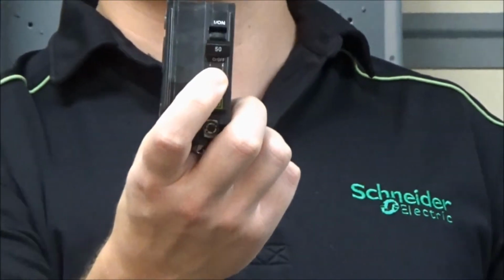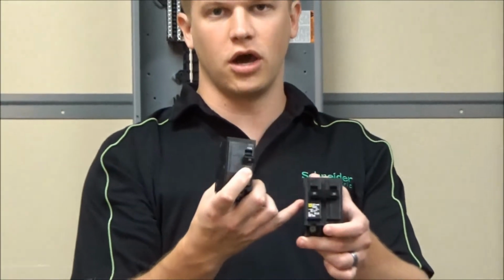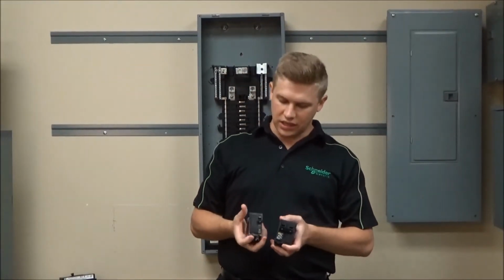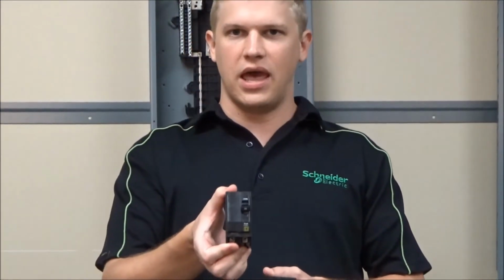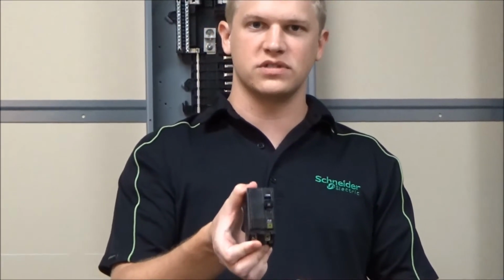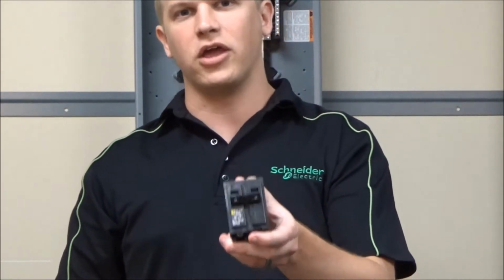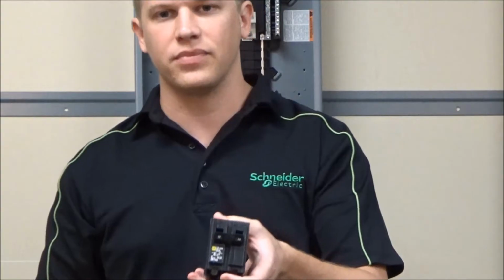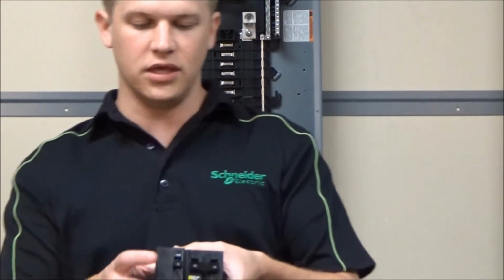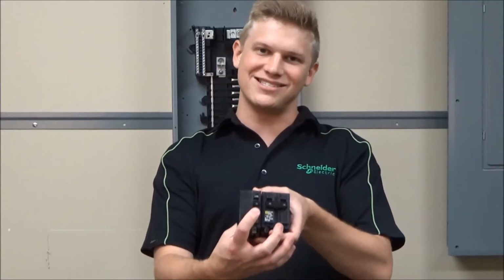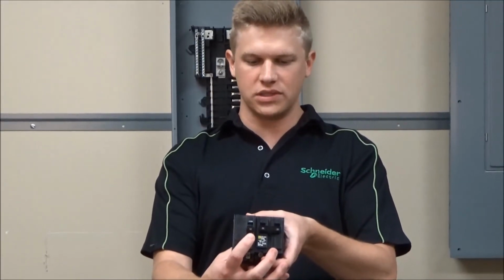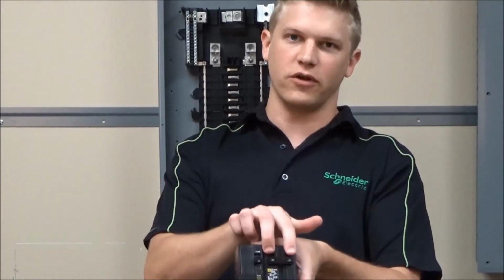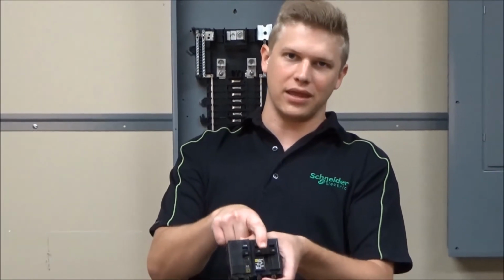First, for the QO, you'll notice there is a Visi-Trip window under the handle. This window, when the breaker trips, will turn orange, and is a feature only on the QO breakers, not on the Homelines. Another difference is the size: the QOs have a 3/4 inch per pole size, whereas the Homelines have a 1 inch per pole size. Also, the QO two-pole breaker has a single handle on its two poles, whereas the Homelines have a handle for each pole, joined by a handle tie.